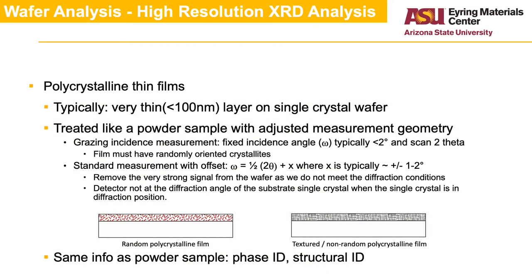Typical polycrystalline thin films are in the 100 nm range, and sometimes thinner. The thinner the sample, the more challenging the measurement becomes. Typically, we would do a grazing incidence measurement, meaning that the X-ray beam is at a very shallow incidence angle and fixed for the duration of the measurement. For such a measurement to be useful, the sample must have randomly oriented crystallites.